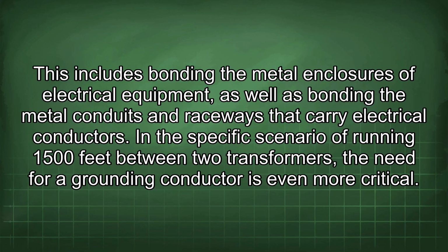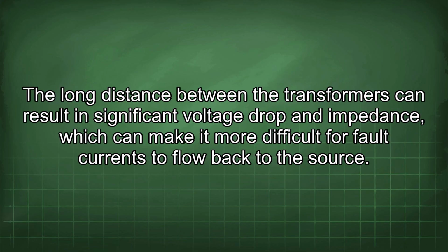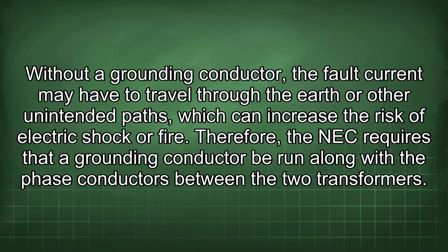In the specific scenario of running 1500 feet between two transformers, the need for a grounding conductor is even more critical. The long distance between the transformers can result in significant voltage drop and impedance, which can make it more difficult for fault currents to flow back to the source. Without a grounding conductor, the fault current may have to travel through the earth or other unintended paths, which can increase the risk of electric shock or fire.